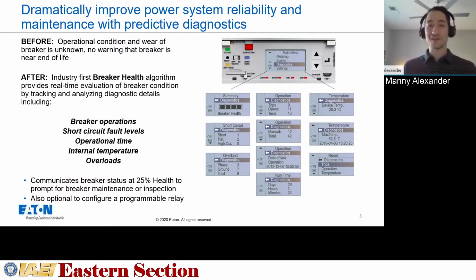So I think Tom would agree that this is a really cool feature. It's one of my favorites. A long-standing question in the circuit protection industry has been, when is the end of life for a molded case circuit breaker? And in reality, it depends on how the circuit breaker is used. Is it operated frequently? What kind of fault events has that breaker seen? What are the environmental conditions of the breaker? Ideally, there would be a way to monitor these variables to predict how long the breaker will operate successfully before it approaches an issue or end of life.